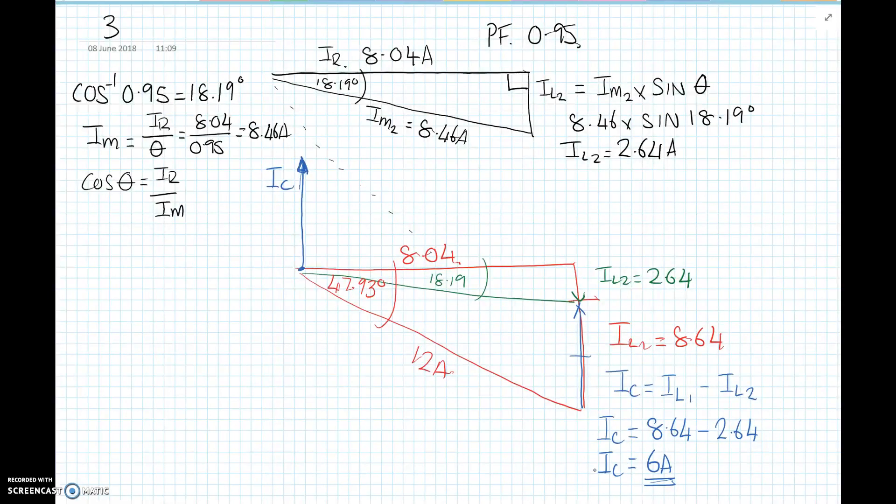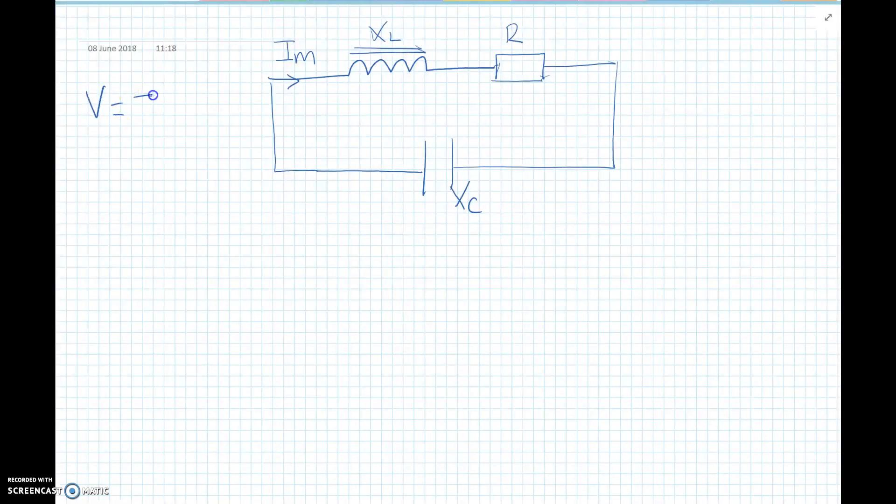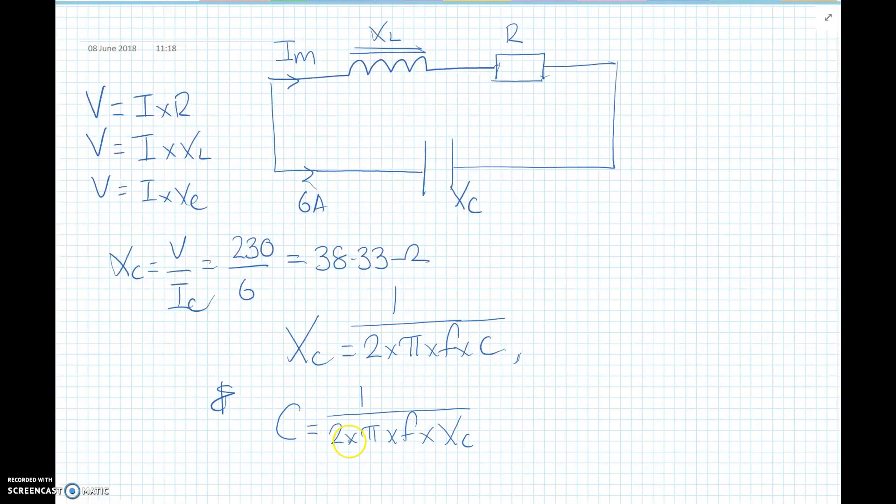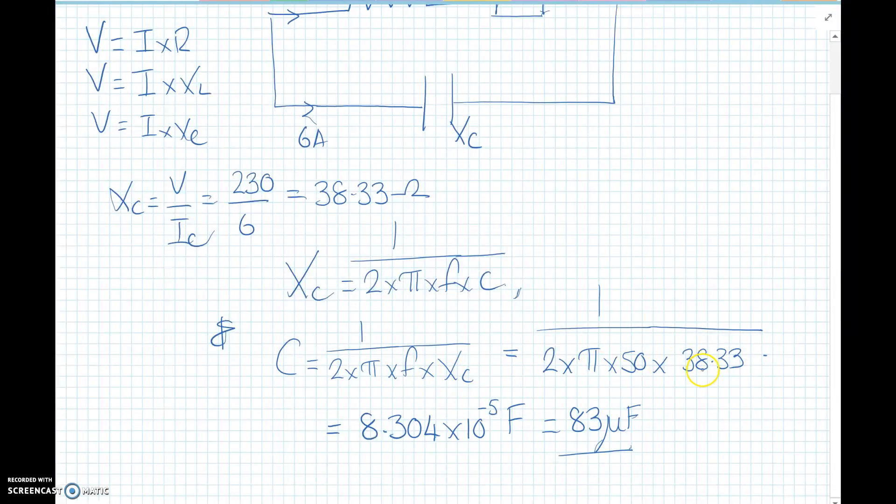So we need 6 amps to go through our capacitor, which takes off on the negative of the inductor, which leaves only 2.64 amps on the inductive circuit. So now we know the current required, we need to select the value of the capacitor. From Ohm's law, V equals I times R, and in AC theory V is I times XL and V is I times XC. We need 6 amps to flow through our capacitor. So we transpose the formula, XC is V over IC, which is going to be 230 over 6, which gives us 38.33 ohms. Capacitive reactance XC is 1 over 2πFC. Rearrange that for C, so C equals 1 over 2 times pi times frequency times reactance. So we've got 1 over 2 times pi, 50 hertz, the reactance is 38.33, which gives us 83 microfarads.